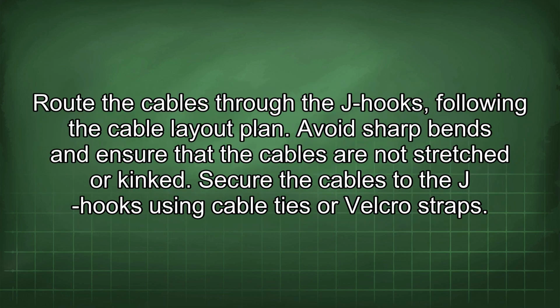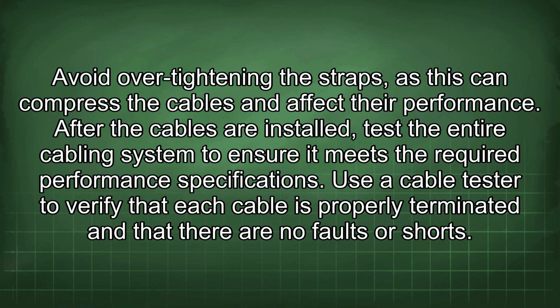Route the cables through the J-hooks following the cable layout plan. Avoid sharp bends and ensure that the cables are not stretched or kinked. Secure the cables to the J-hooks using cable ties or Velcro straps. Avoid over-tightening the straps, as this can compress the cables and affect their performance.